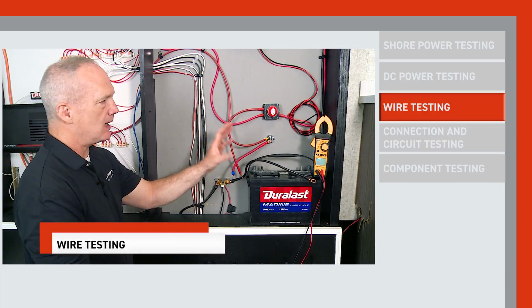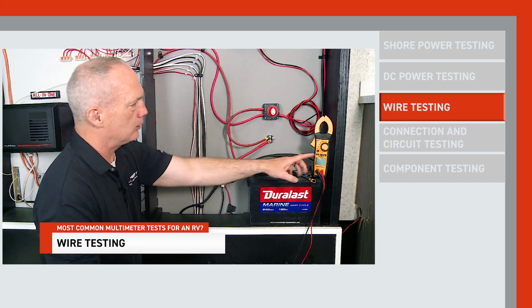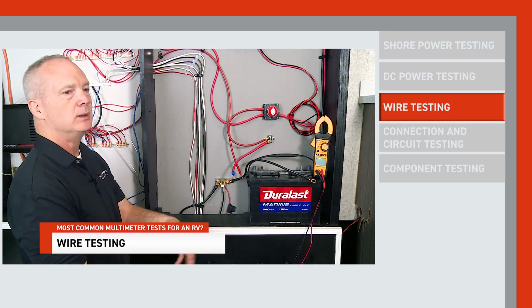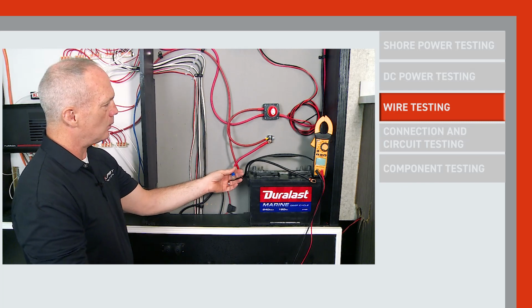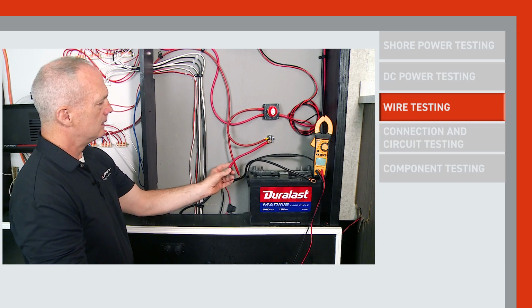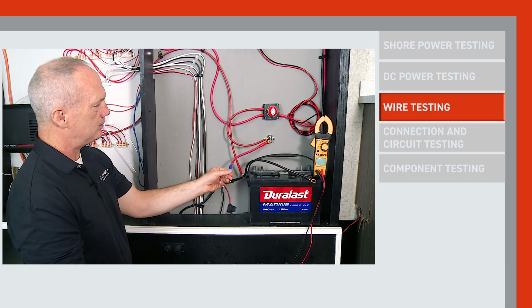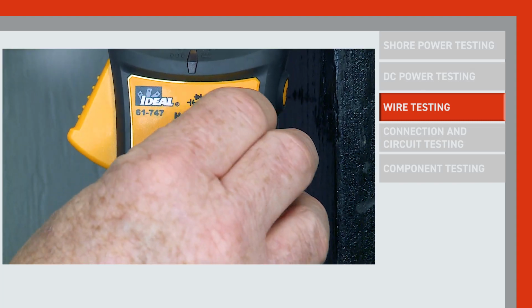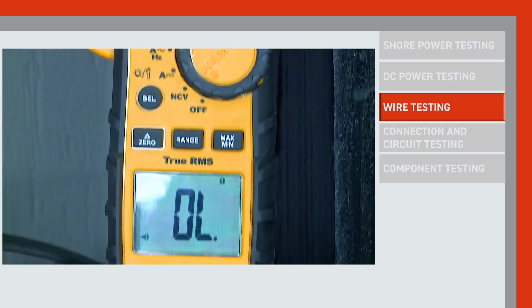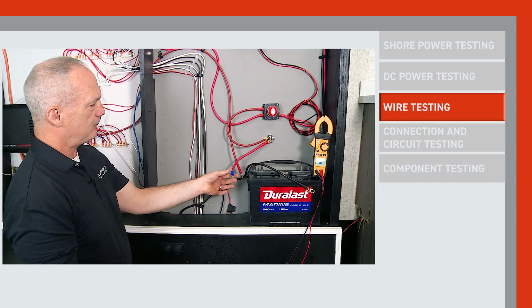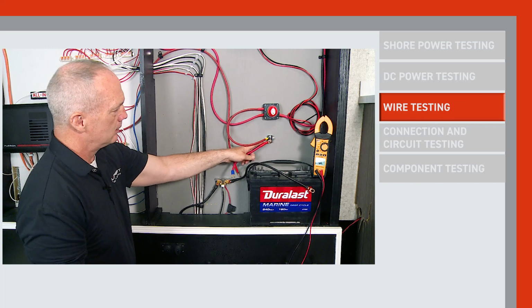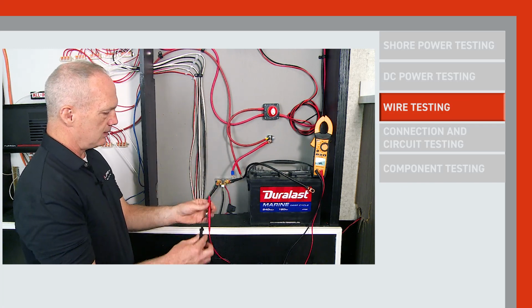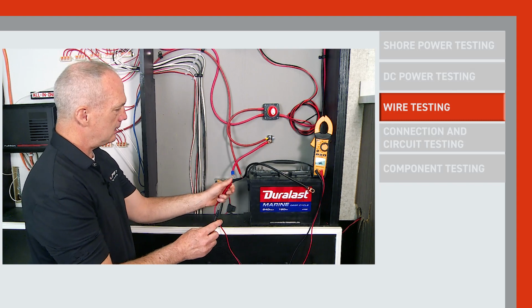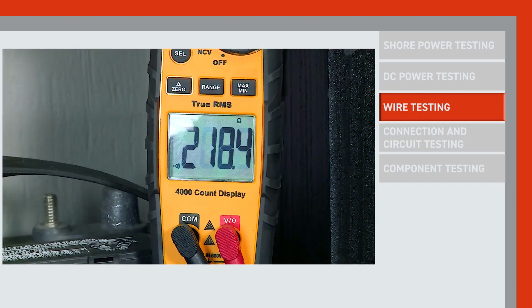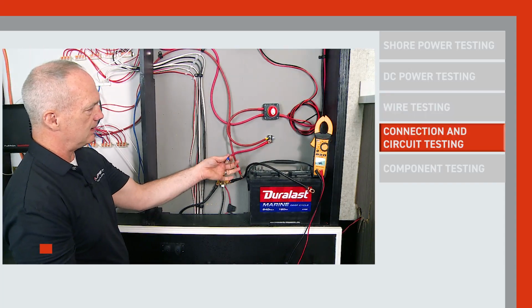For the next couple tests, I'm going to set the multimeter to read ohms, which is resistance, or connectivity, making sure the wiring you're checking has complete connectivity from point A to point B. Let's change this dial to ohms, and you'll see 0 and an L there. For the first test, I'm going to check the continuity in this short red wire by putting one lead here and one here. It reads 0.0 ohms, which is perfect connectivity from point A to point B.